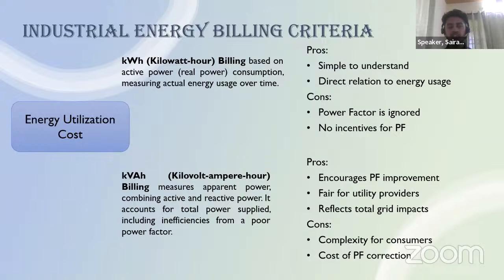The cost that is charged for this is in two categories. The first is kilowatt hour billing. That is the real power that we are exactly using, and it will be directly considered and billed based on kilowatt hours. The advantage of kilowatt hour billing is that it is very simple to understand. Even if you see the Tamil Nadu grid board's domestic bills, you will get to know about kilowatt hours only. They directly give the difference of meter readings, how many kilowatt hours you have consumed over the duration of 2 months, and they multiply it by the unit cost factor and give you the amount. It is directly related to the energy usage. Whatever you consume, you pay for that.